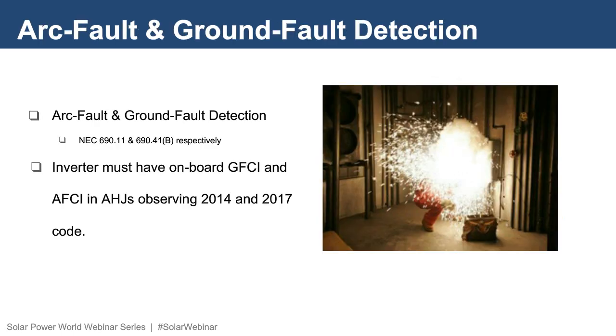Arc fault detection was introduced in the 2011 code cycle. At that time, products were not readily available, resulting in little to no enforcement of the requirement. Over time, products became available such as string inverters with onboard arc fault detection. Ground fault detection was introduced in the 1987 code cycle and has since seen many modifications. Originally placed in 690.5 and 690.35c for ungrounded systems, it was moved to 690.41 in the 2017 code cycle. Ground fault detection is an important feature to assist in the prevention of fires. For system designers, installers, and owners, inverters incorporating these two features simplify system design, operation, and maintenance.